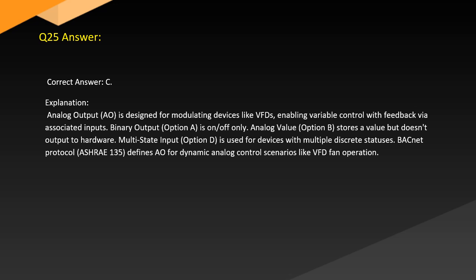Answer. Correct answer: C. Explanation. Analog output is designed for modulating devices like VFDs, enabling variable control with feedback via associated inputs. Binary output, option A, is on-off only. Analog value, option B, stores a value but doesn't output to hardware. Multi-state input, option D, is used for devices with multiple discrete statuses. The BACnet protocol, ASHRAE 135, defines analog output for dynamic analog control scenarios like VFD fan operation.